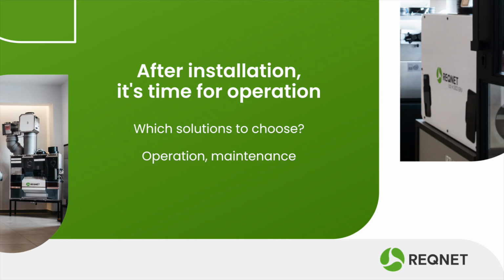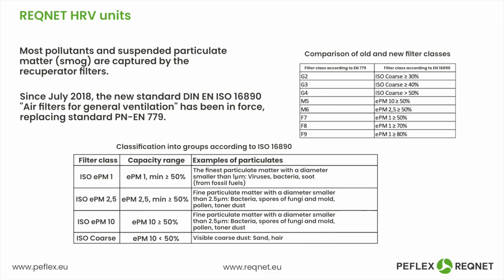Regarding operation, we have filters available that can be installed either in the ventilation unit or in an external filter box. And as a minimum, the quality class of the filter that should be installed in ventilation units is an M5 class filter, which captures 50% of PM10 dust particles.